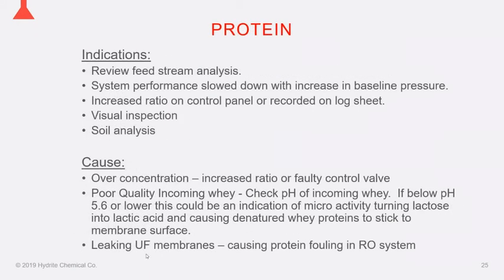The next foulant we're going to look at is protein. Again, this is going to have similar symptoms from a hydraulics perspective as far as the increase in baseline pressure.